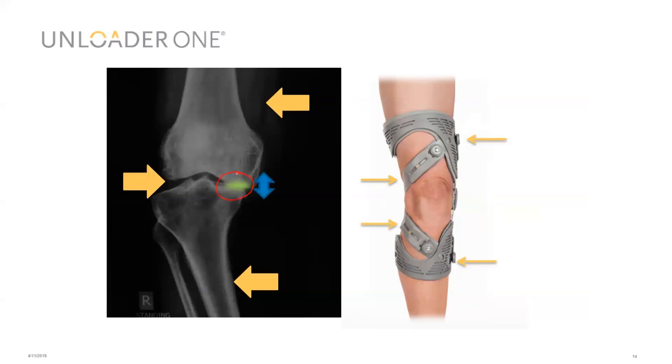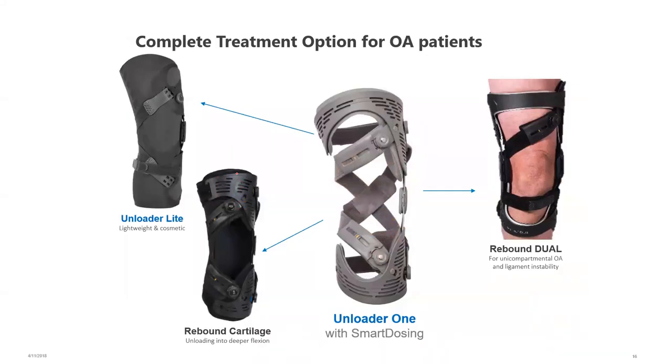Many patients report discomfort descending slopes and stairs — activities where you get very high pressure peaks in the joint. We have a range of orthoses for different patient types within our osteoarthritis range. On the right is the Rebound Dual, designed to combine unloading technology using a DFS strap with ligament control, and it can also be adjusted either side to accommodate varus or valgus angulation. On the left is the Unloader Lite — a very cosmetic, sleeve-based brace weighing about 296 grams, designed to fit under clothing and be quick and easy to fit.